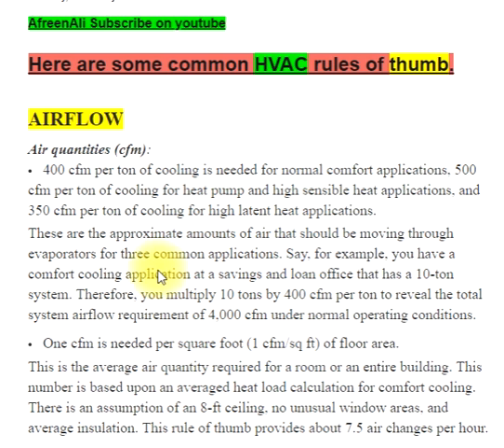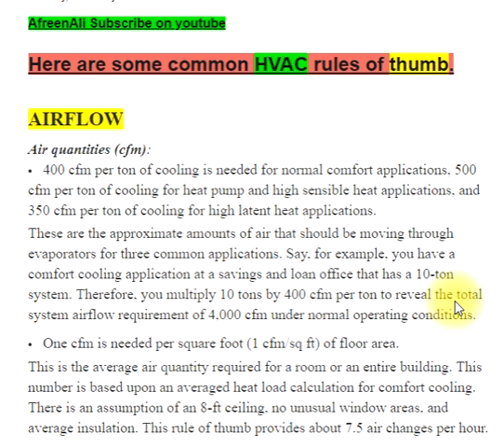For example, you have a comfort cooling application at a savings and loan office that has a 10-ton system. Therefore, you multiply 10 tons by 400 CFM per ton to reveal the total system airflow requirement of 4,000 CFM under normal operating conditions.